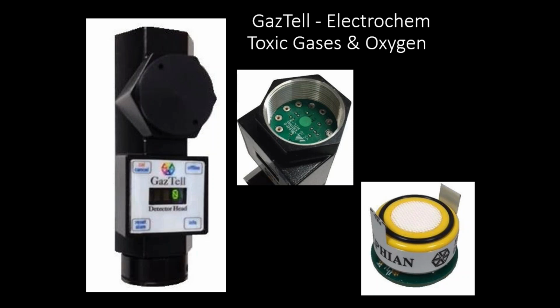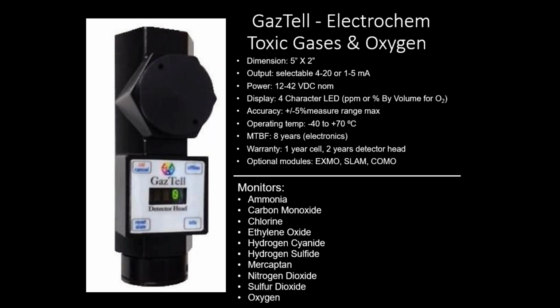The way the electrochemical cell works is like the catalytic bead. It's a plug-in PC board. When you remove the flame arrestor, it exposes the PC board that you plug the cell into. The beauty of this is that you can buy one gas detector head, 365-450-501 is a GazTell detector head part number.